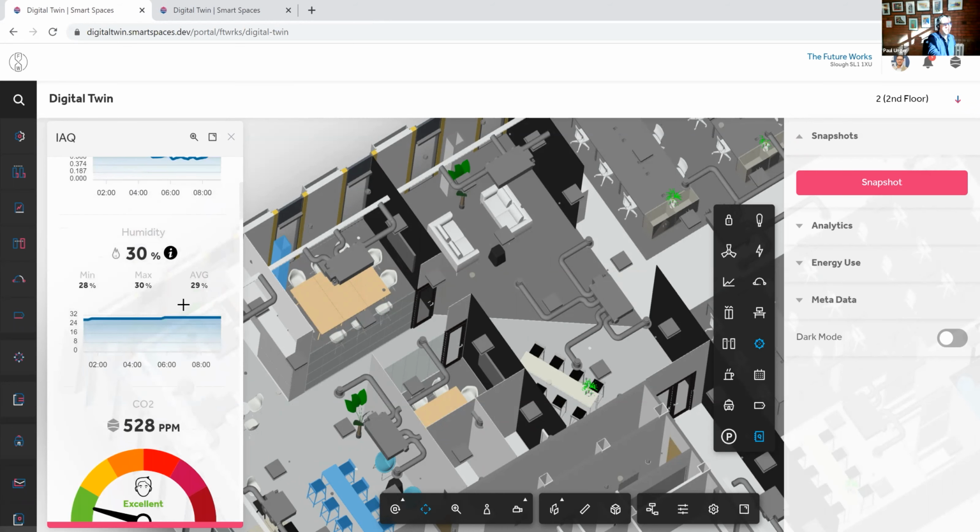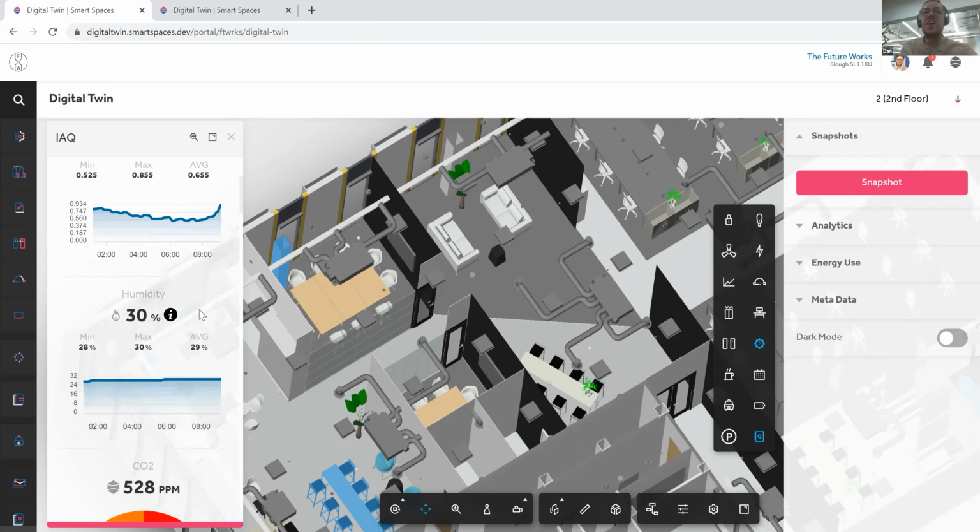Why does that go up after 8 o'clock in the morning? That's a really good question. Sometimes we find that people have walked into that room, so it could be your aftershave. One of the funniest ones is the banana. If you open a banana and eat a banana in that room, it sends the volatile organic compounds off the charts. So yeah, there are some funny anomalies.